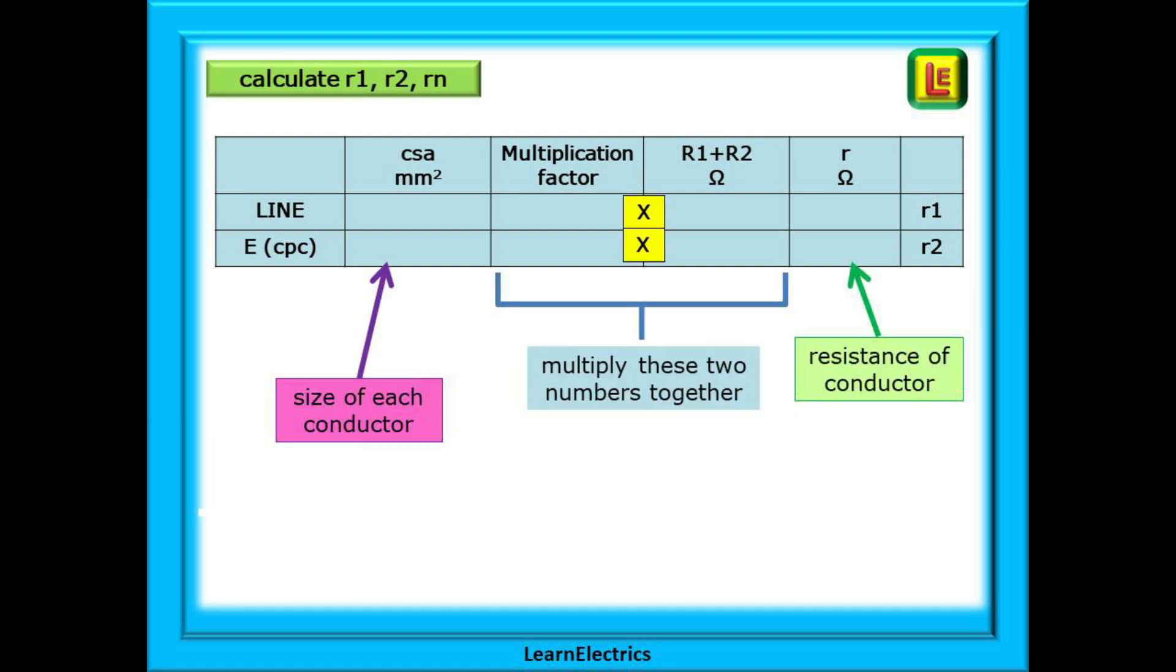We are going to enter the size of the conductors first, and then we will find a multiplication factor. If we then multiply this by the big R1 plus big R2 value, out will pop the end-to-end resistance of each conductor, the little R1 and the little R2.